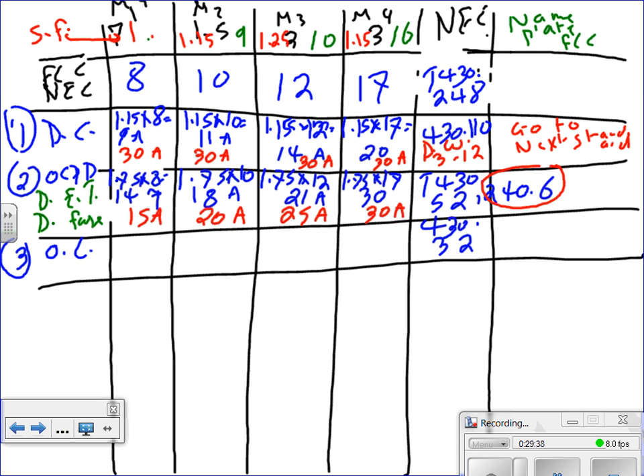And also there's the temperature rise. If you see the temperature rise, motors with a marked temperature rise of 40 or less, 1.25. All other motors, 1.15. Temperature rise, guys, is how high the windings inside the motor can reach before the motor fails. The whole idea of overload is to protect motors from heat, because heat creates smoke. Smoke burns things, and when the motor is burned, it cannot run. So if you have a fan and the motor is smoking, you don't expect the fan to give you air, right? So motors marked with a temperature rise of 40 or less, 1.25.